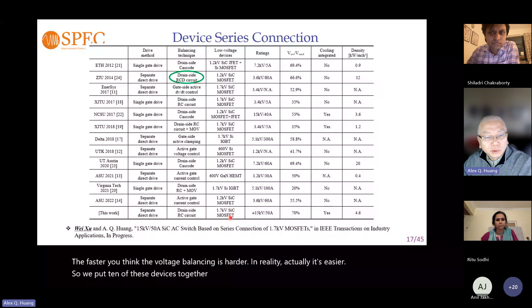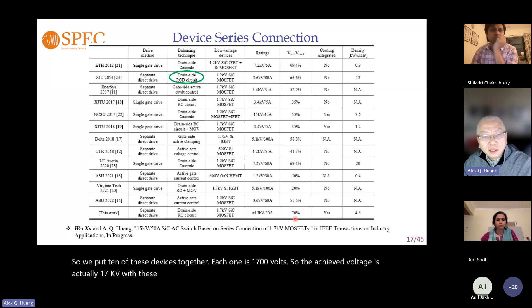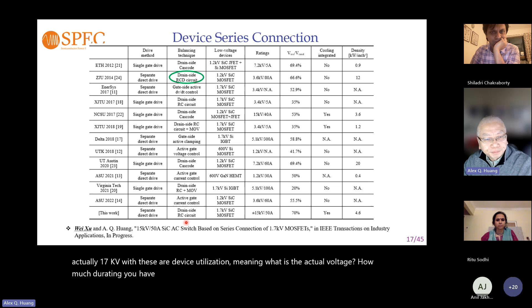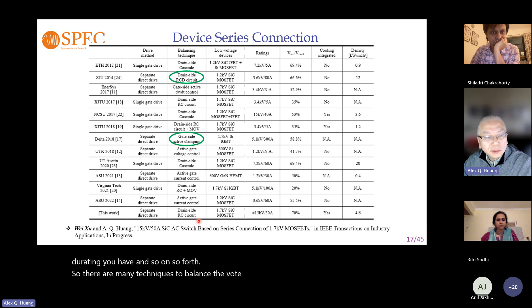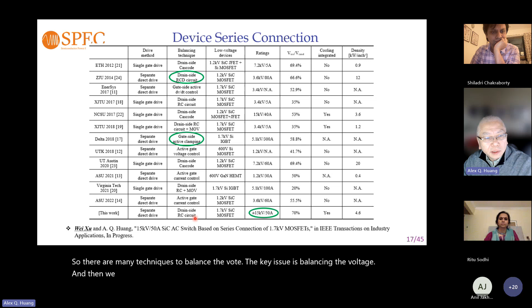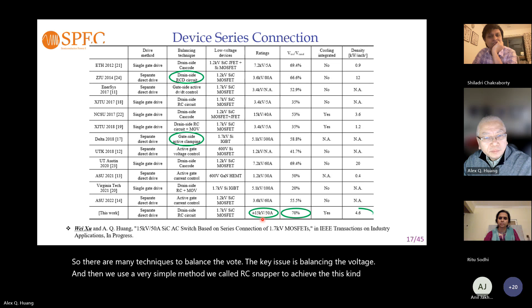We put 10 of these devices together, each one 1700 volts, so the achieved voltage is actually 17 kV. These are device utilization figures, meaning what the actual voltage is, how much derating you have, and so on. There are many techniques to balance the voltage—the key issue is balancing the voltage—and we used a very simple method we call the RC snubber to achieve this kind of performance.